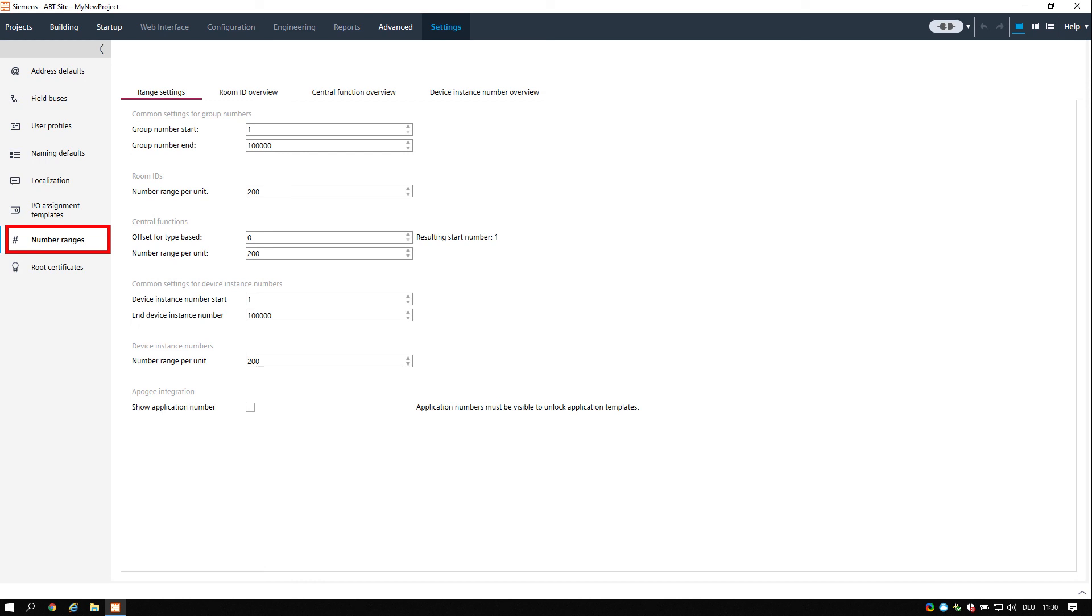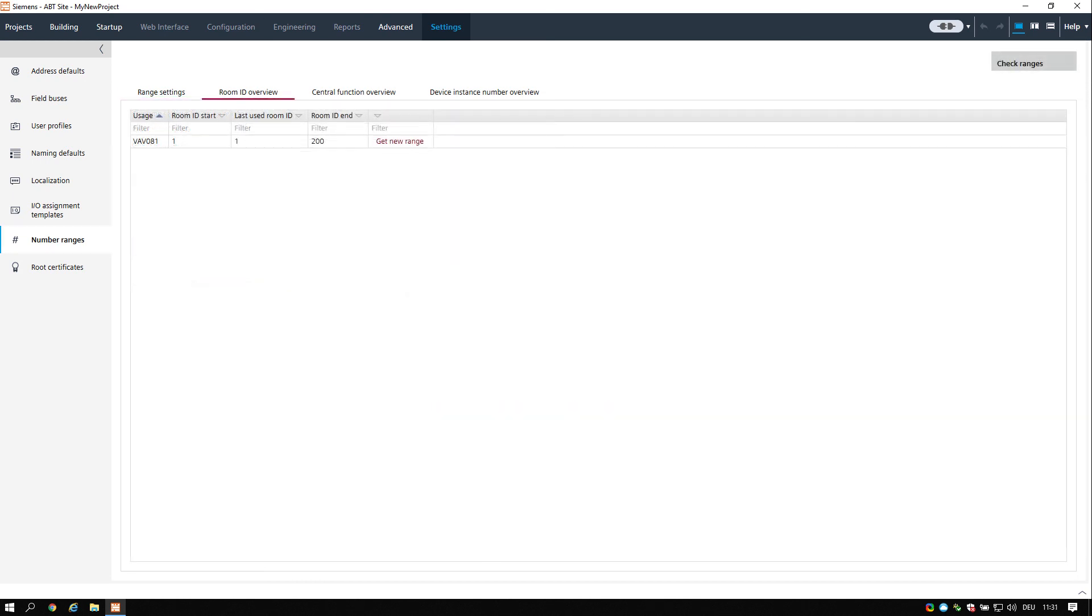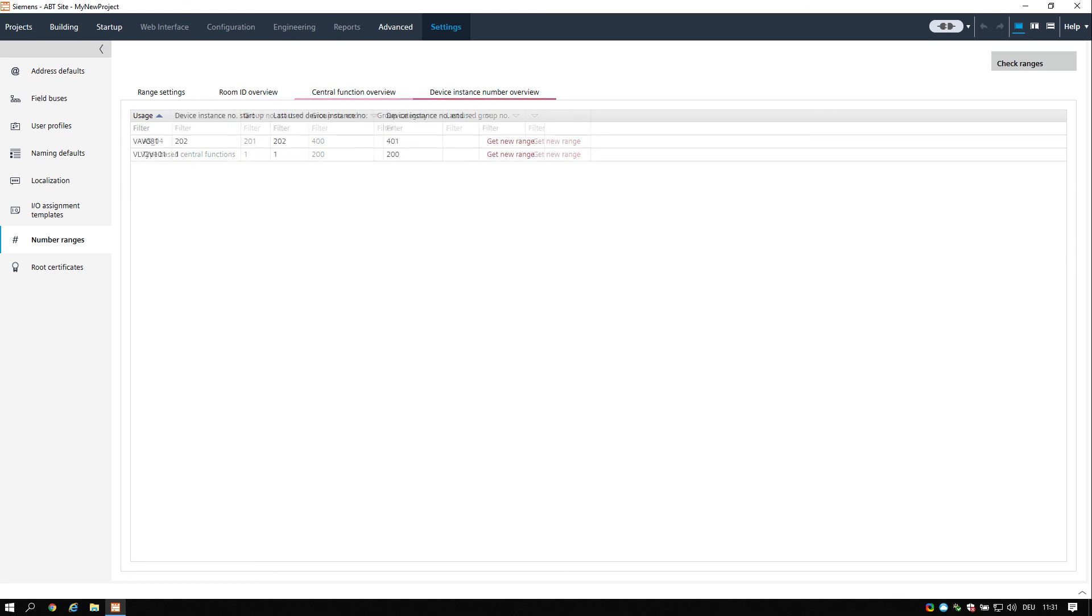The number ranges task allows you to define the number ranges for room IDs, central functions, and device instance numbers and provides an overview of the used and defined number ranges. Room IDs and central function numbers must be unique within the BACnet system.